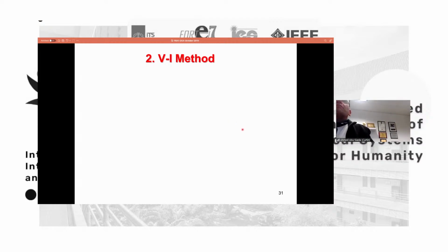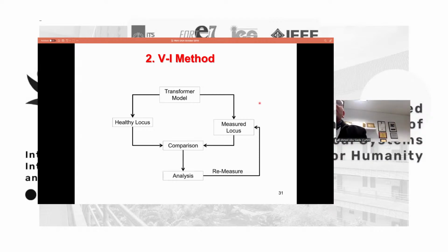The last point, I know I may have exceeded my time, but it's only 3 or 4 slides. The last point is, how about if we work on a power transformer? Can we just exclude the frequency, so we are not looking at a spectrum of a very high range of frequencies? I will perform the test at 50 hertz, measuring the voltage and the current of the transformer. The advantage of this technique is you can perform it at the power frequency, 50 hertz. So there is no need to use an external source or to disconnect your transformer. The other point is you can do it every cycle, which is 20 milliseconds if your frequency is 50 hertz.